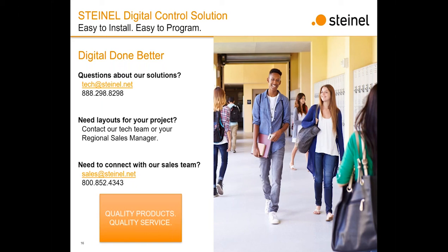Correct. If the DCS is indoors connected to outdoor devices, how long can the wiring go? 300 meters. Okay. Are there power boosters available to boost more? No, we don't have any that we're offering at this time. We've tried it with a few that are in the marketplace, but we haven't released them where we're selling them yet.